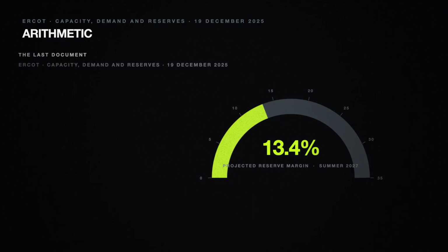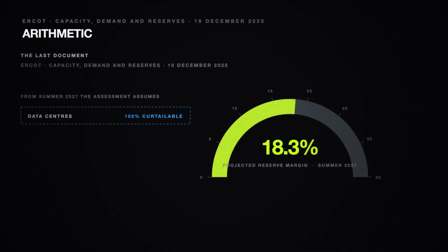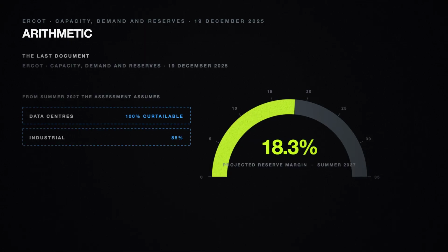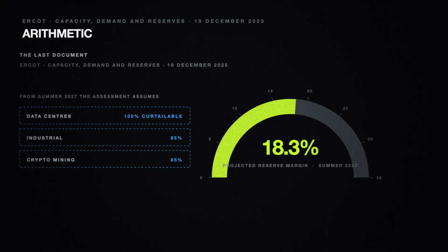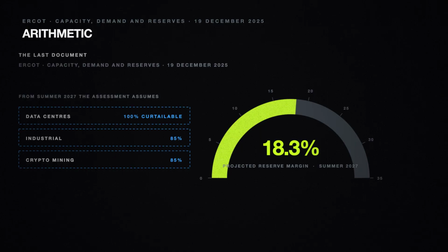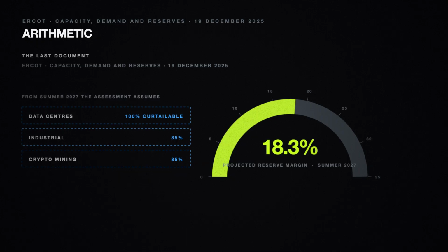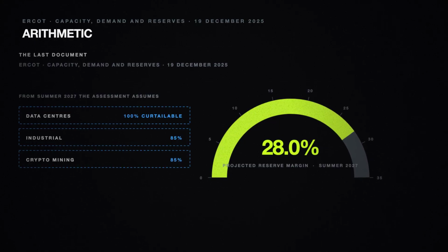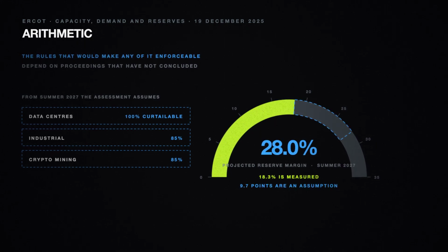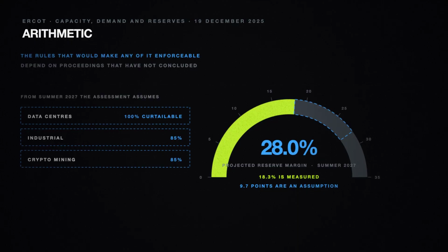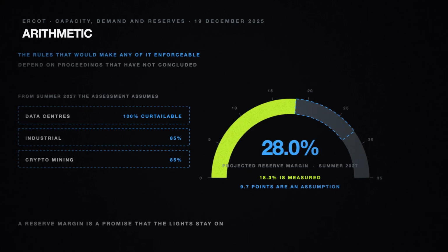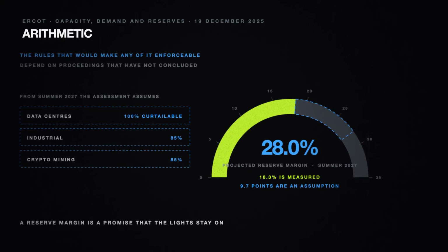Which brings us to the last document. In December 2025, the Texas grid operator published its official assessment of whether the state will have enough power. Beginning in the summer of 2027, that assessment assumes data centers are 100% curtailable, industrial load 85%, crypto mining 85%. Those assumptions carry the projected reserve margin from 18% to 28%. In the same document, the operator notes that the rules making any of it enforceable depend on regulatory proceedings that have not concluded. A reserve margin is a promise that the lights stay on. That one is doing arithmetic on a rule that does not exist yet.